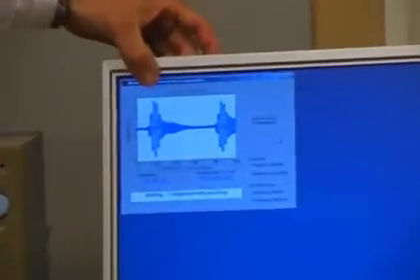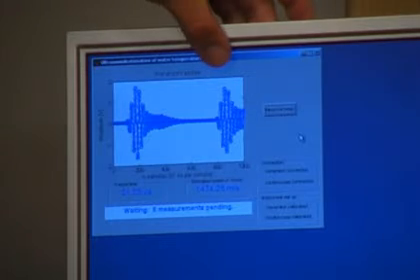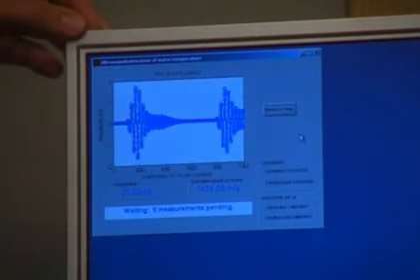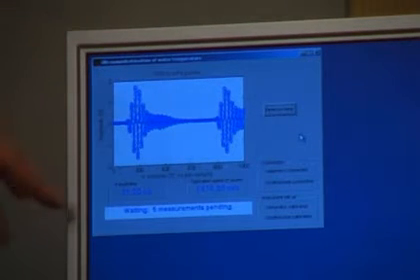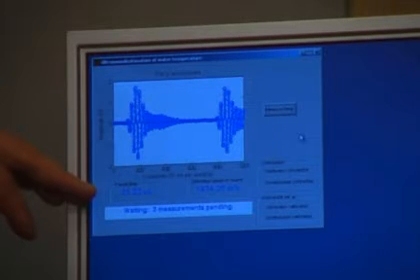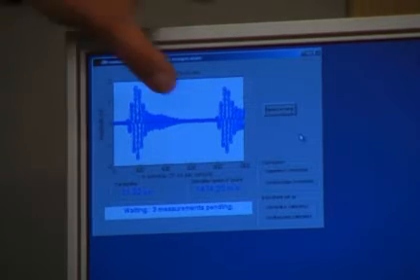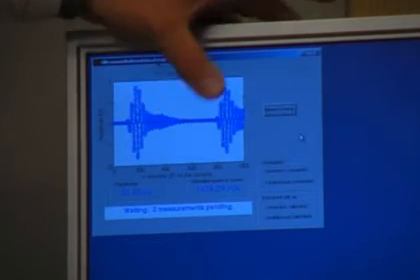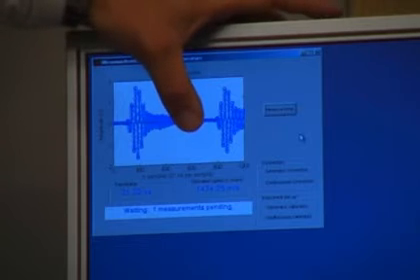We take the transit time between the two pulses to estimate the speed of sound in water. We have, in this case, about 21 microseconds in transit time, and that gives us 1474 meters per second.